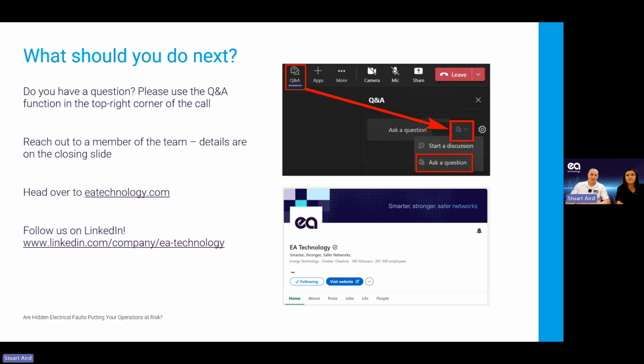Certainly we would definitely recommend that you do a partial discharge survey of any switch you're just about to operate. If you've got a high level of partial discharge, particularly surface PD, and you're going to be racking down an old circuit breaker, you don't want to be doing that if you've got high levels of ultrasonic activity coming out of the spouts area, for instance. So it certainly will help you keep yourself safer, I would feel. So we certainly recommend that you do that before any kind of switching operations.